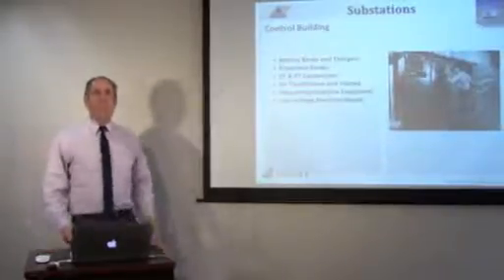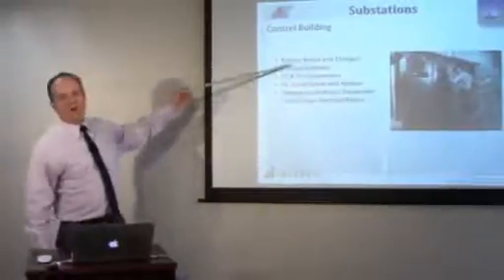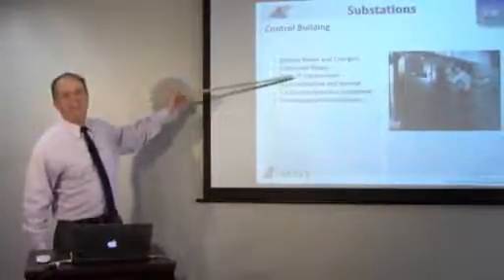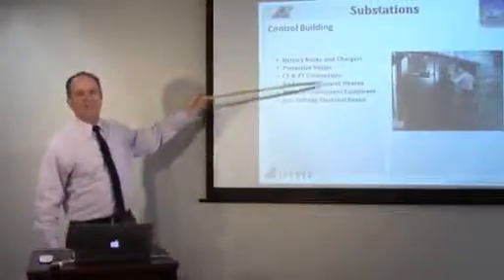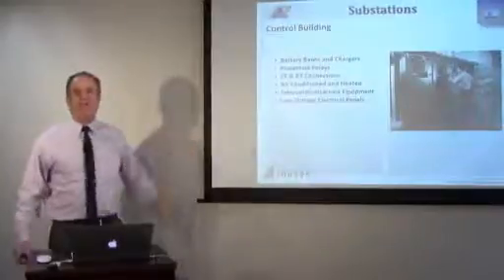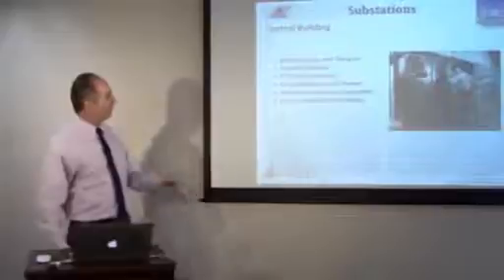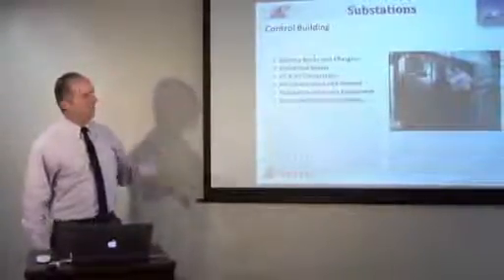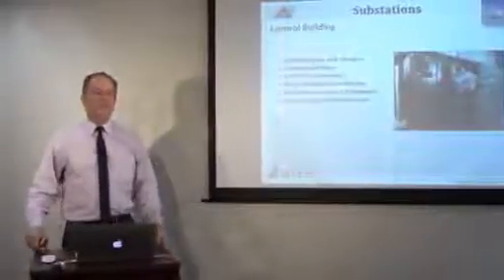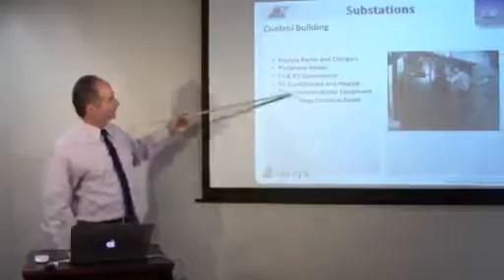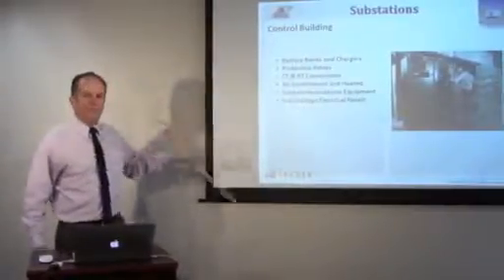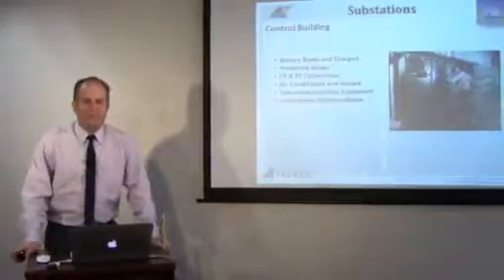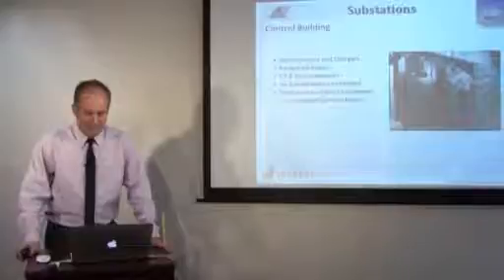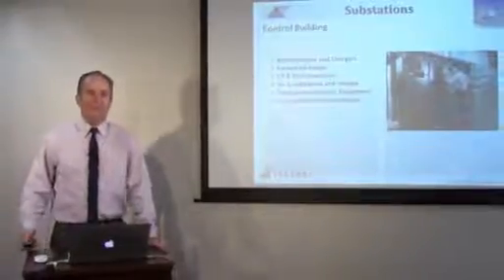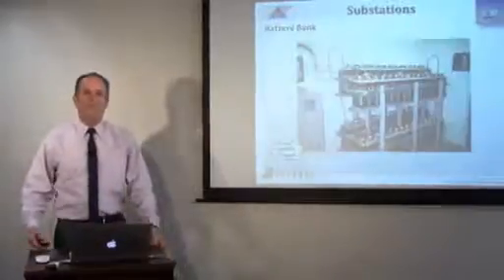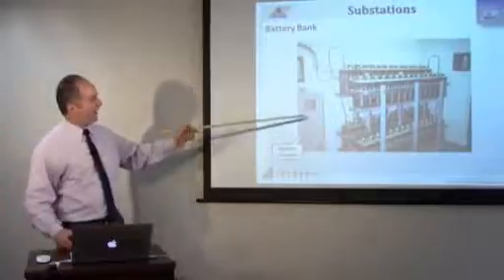Inside of a control building, you'll find the equipment associated with batteries and chargers and protective relays and CT and PT connections to the relays. It's air conditioned and heated, because you might find telecommunications equipment and computers and things of that nature that are sensitive to temperature extremes. You have the low voltage panels for lighting and battery chargers and that. So in the control building, you'll find where the sensitive equipment is, or the connections, or where all the metering and protective relay and telecommunication equipment reside. Here's a picture of a typical battery bank in a substation.